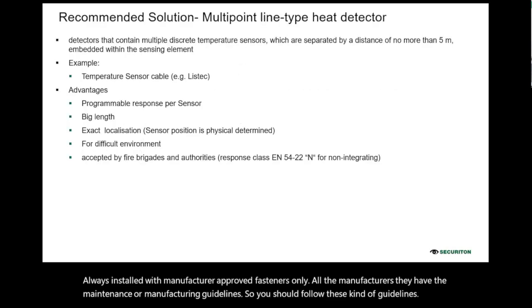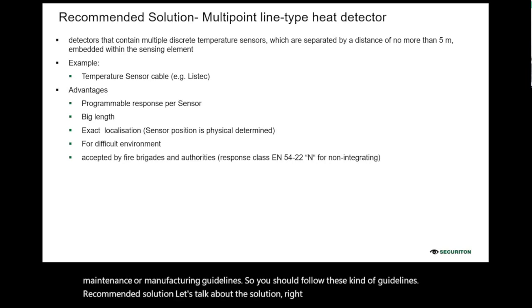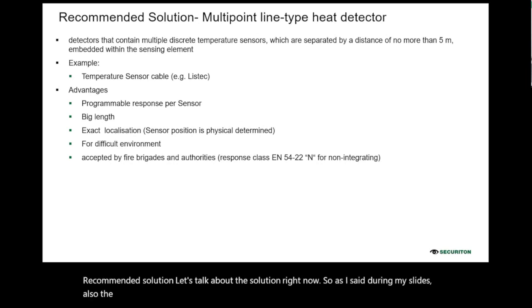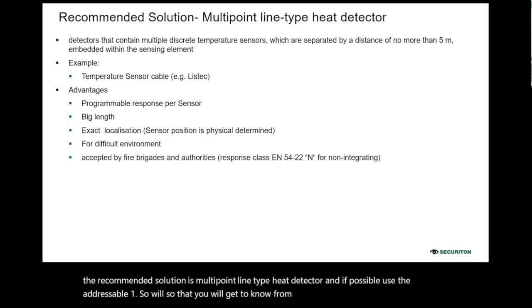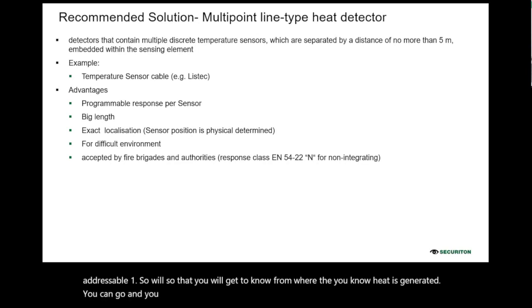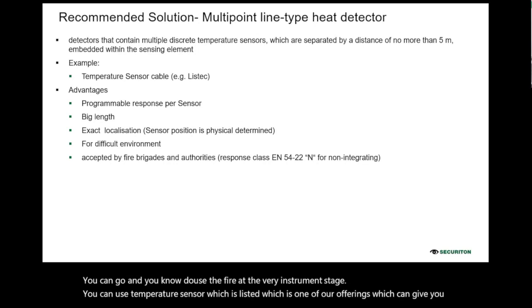Recommended solution. Let's talk about the solution right now. As I said during my slides also, the recommended solution is a multi-point line type heat detector. And if possible, use the addressable one so that you will get to know from where the heat is generated. You can go and douse the fire at the very incipient stage. You can use a temperature sensor, which is Listec, which is one of our offerings, which can give you the address as well as the live temperature monitoring.